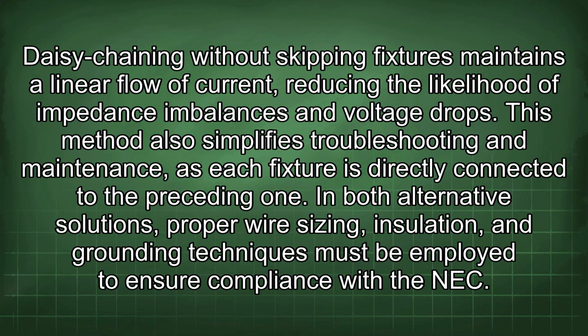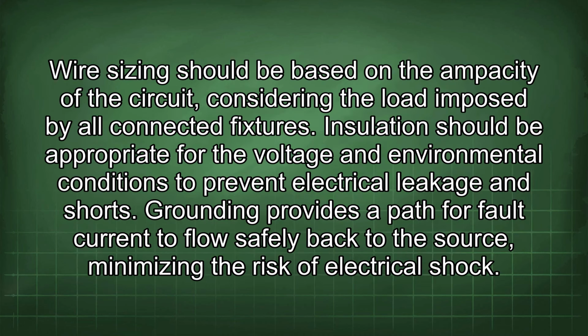In both alternative solutions, proper wire sizing, insulation, and grounding techniques must be employed to ensure compliance with the NEC. Wire sizing should be based on the ampacity of the circuit, considering the load imposed by all connected fixtures. Insulation should be appropriate for the voltage and environmental conditions to prevent electrical leakage and shorts. Grounding provides a path for fault current to flow safely back to the source, minimizing the risk of electrical shock.